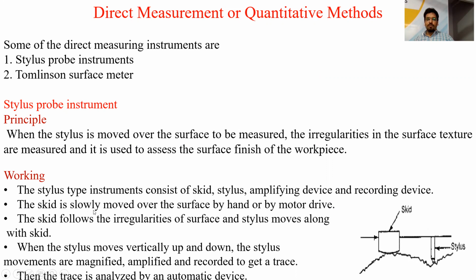Second, the skid moves slowly over the surface by hand or motor. This skid can be moved over the surface whose roughness is to be measured with the help of hand or by a motor itself. The skid follows the irregularity of the surface and the stylus moves along with the skid.